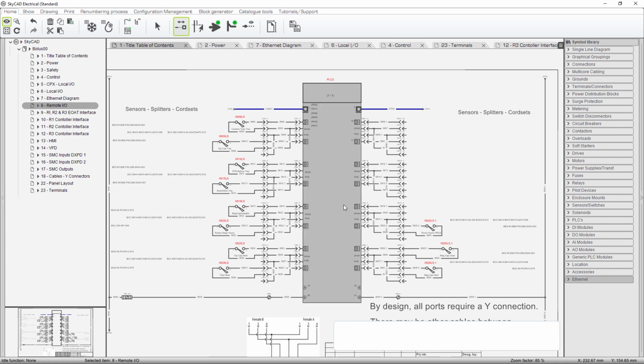These are inputs only. And by the way, I know that looks like a limit switch, but that is technically a solid state sensor. This software didn't have a symbol for a proximity switch that had a diamond around it like you typically see, but it does the same thing. So I could have gone and created another symbol. I didn't. I just used these. So keep in mind that these are solid state sensors, all of them. And I will use up these 4 spots right here before I'm done. So I can have 4 more inputs here.